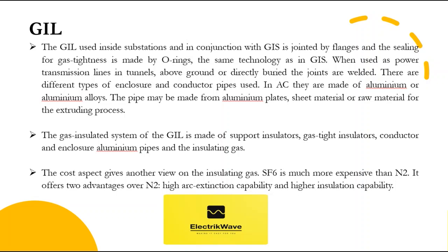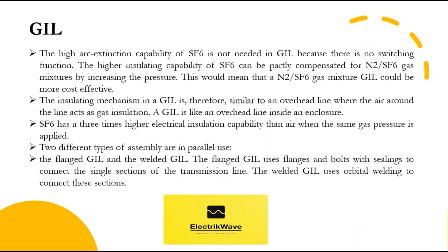The gas insulated system of the GIL is made of support insulators, gas-tight insulators, conductor and enclosure aluminum pipes, and the insulating gas. SF6 is much more expensive than nitrogen, but offers two advantages over nitrogen: high arc extinction capability and higher insulation capability. The high arc extinction capability of SF6 is not needed in GIL because there is no switching function. The higher insulating capability of SF6 can be partly compensated for by nitrogen or SF6 gas mixtures by increasing the pressure, making a nitrogen or SF6 gas mixture GIL potentially more cost effective. The insulating mechanism in a GIL is therefore similar to an overhead line where air acts as gas insulation — a GIL is like an overhead line inside an enclosure.